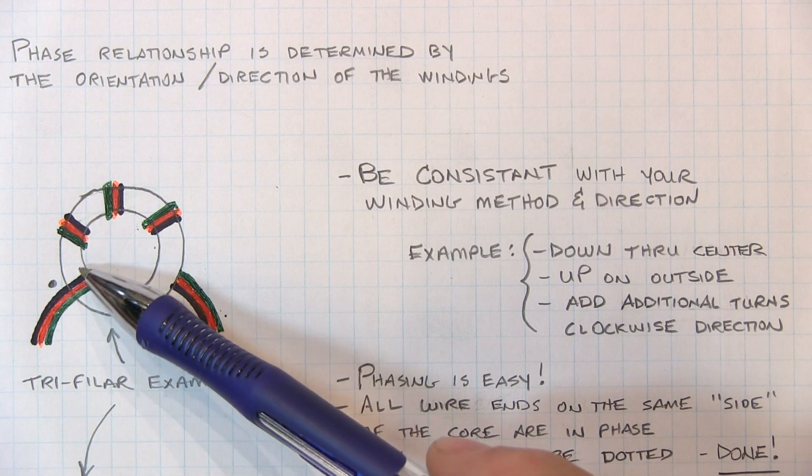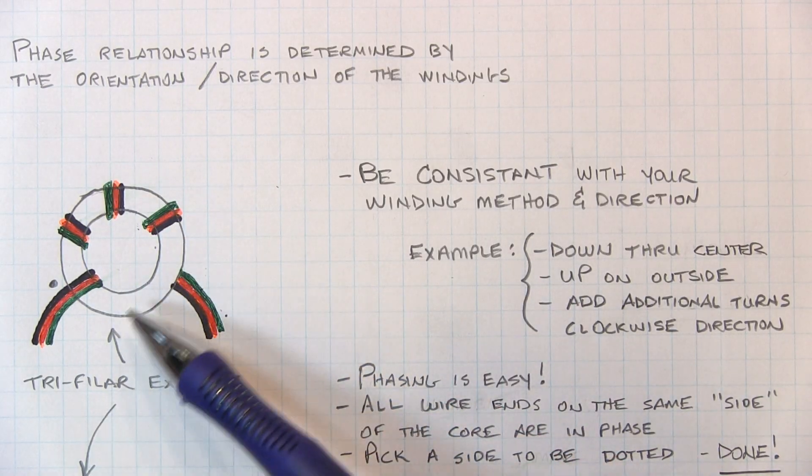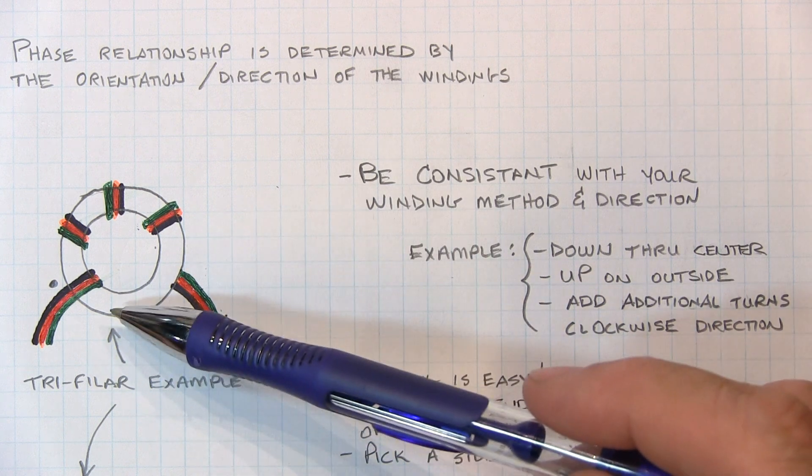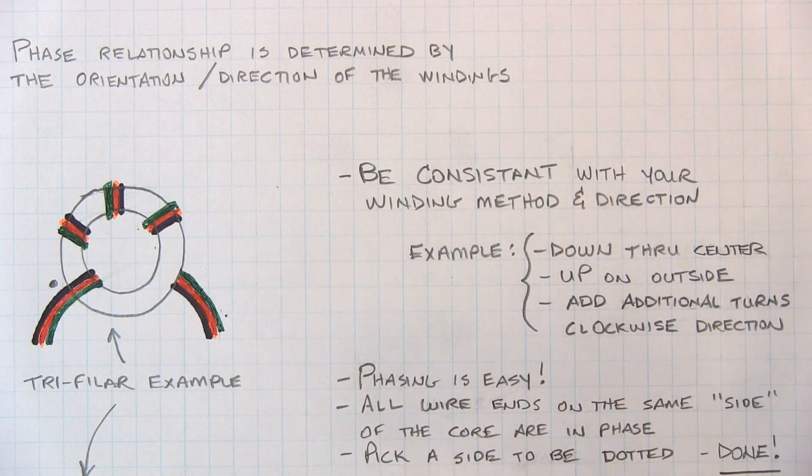Be consistent in the direction in which you wind the turns, and also be consistent in the direction that you add additional turns going around. Don't go around the other way, for example. If you're consistent with every one of the windings that you add to the transformer, then it's real easy to determine the phasing.